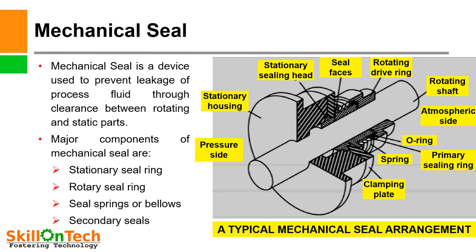A picture of a typical mechanical seal arrangement is shown. Here you can see the pressure side and the atmospheric side. This is a stationary housing and this is a rotating shaft. This is the rotating driving unit of the seal, and this is the stationary seal. This is the seal face where they are mating. This is the spring, which provides compression to the seal faces. And this is the primary sealing ring and this is the clamping plate.